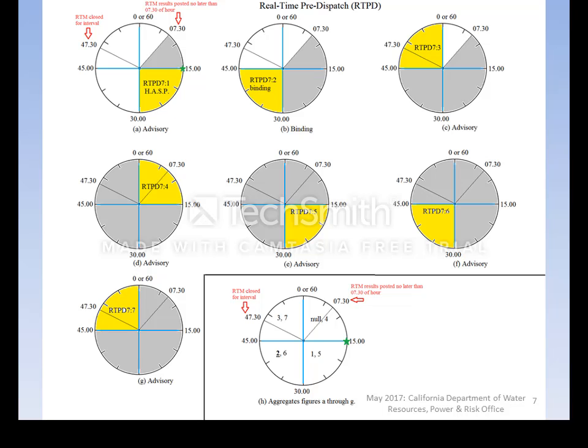HASP or PD7 follows approximately the same timeline each hour for all 24 hours each day. At no later than the 47-minute-30-second mark of each hour, PD7 samples market results including generation awards, self-schedules of supply and demand, state estimator solution, CAISO forecast of CAISO demand, and scheduled exports to adjacent balancing areas. During the following few minutes but no later than the 7-minute-30-second mark of the next hour, PD7 performs an iterative computation to identify the most optimal feasible unit commitment solution. At that mark, the unit commitment decision published as 15-minute market results is made available individually to generation units through ADS and globally through OASIS.